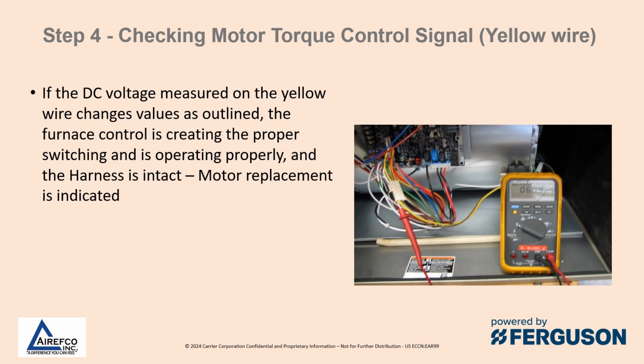If the DC voltage measured on the yellow wire changes values as outlined, the furnace control is creating the proper switching and is operating properly, and the harness is intact. Motor replacement is indicated.